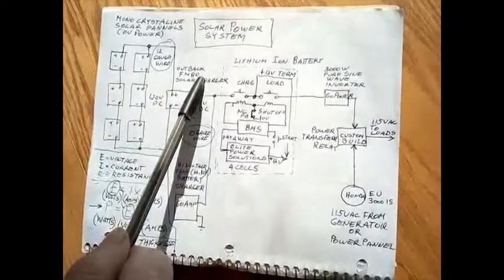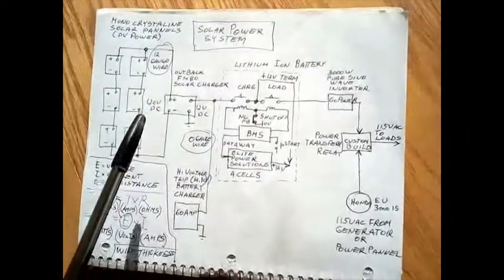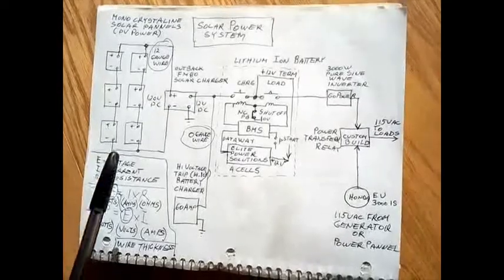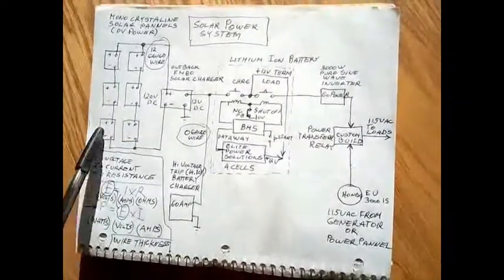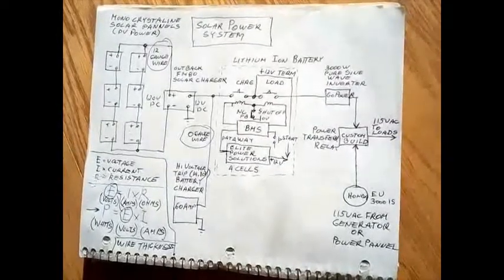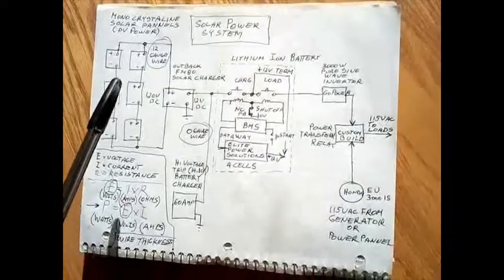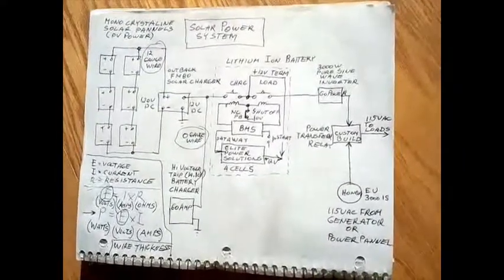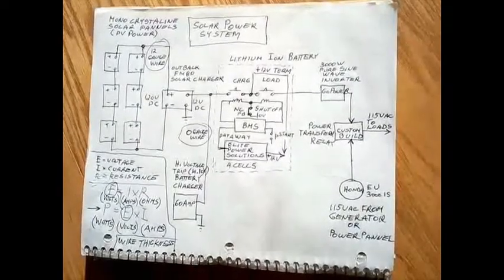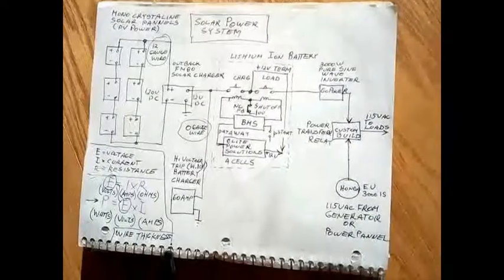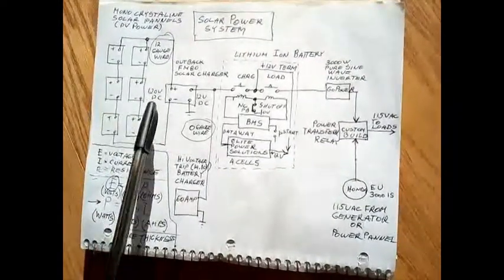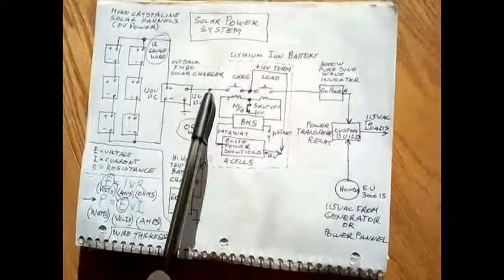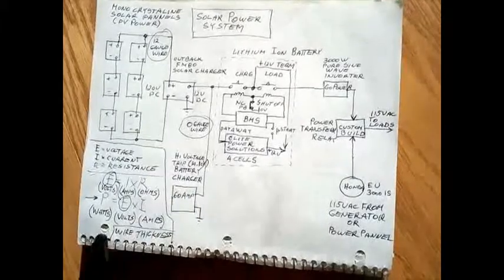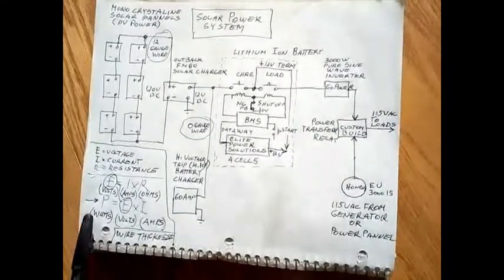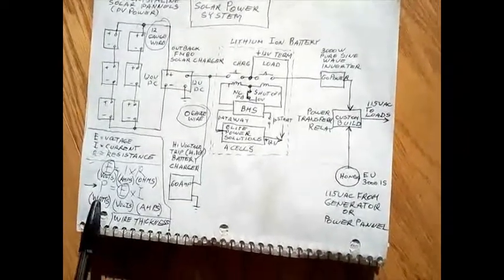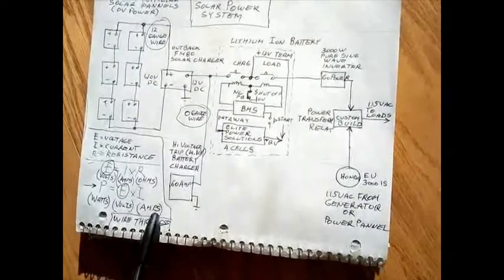For the Outback FM80, the open circuit voltage is 150 volts. So in this case here, each of these panels is 42 volts. So we've got under 150 volts by quite a bit. So that gives us a little bit of a margin of error. At this point, I'd like to discuss the wire thicknesses required for the input circuit and compare it to the wire thicknesses of the output circuit. As you know, or might know, power in watts is equal to volts times amps.